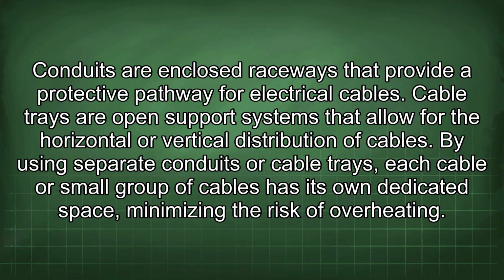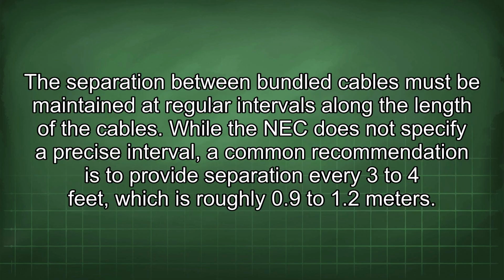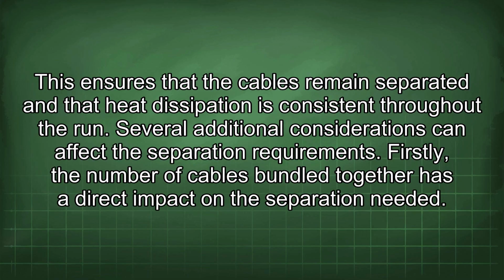The separation between bundled cables must be maintained at regular intervals along the length of the cables. While the NEC does not specify a precise interval, a common recommendation is to provide separation every 3 to 4 feet, which is roughly 0.9 to 1.2 meters. This ensures that the cables remain separated and that heat dissipation is consistent throughout the run.